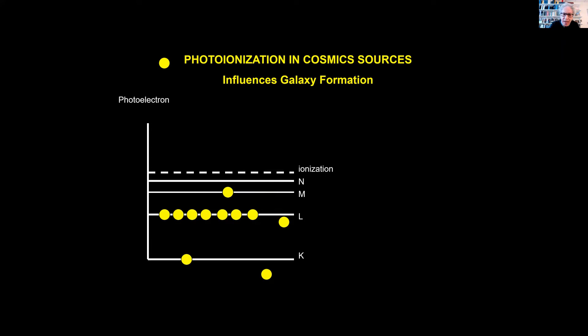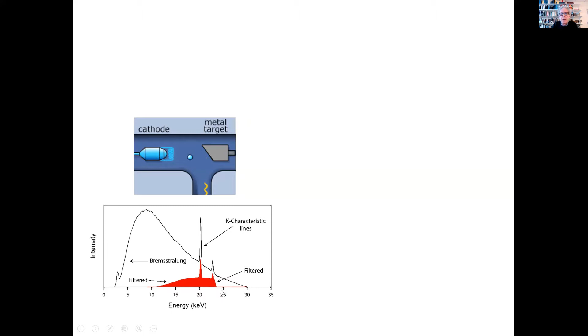So here we are again, and as Madan showed you before, you start off with a bremsstrahlung spectrum. This cutoff at the low energy end is due basically to the self-absorption in the target. But because people have wanted to reduce the total dose to the patient, you would filter it with thick filters, aluminum, rhodium in particular. We'll actually do some filtering at the low energy end and at the high energy end from the rhodium K-alpha. But what if we had a monochromatic X-ray source? Here you can see the same filtered spectrum. This would probably be from a tungsten target, but if we had a monochromatic line, we'd have less tissue absorption. You know that 95% of the radiation coming from this total continuum source is absorbed in the breast.